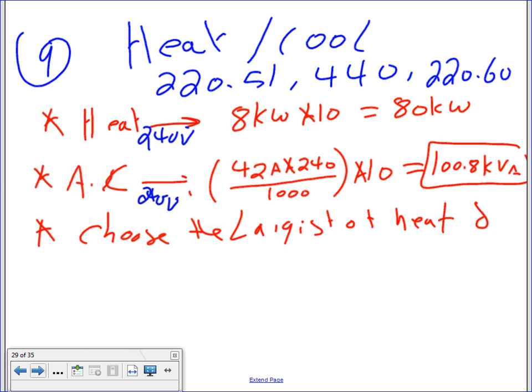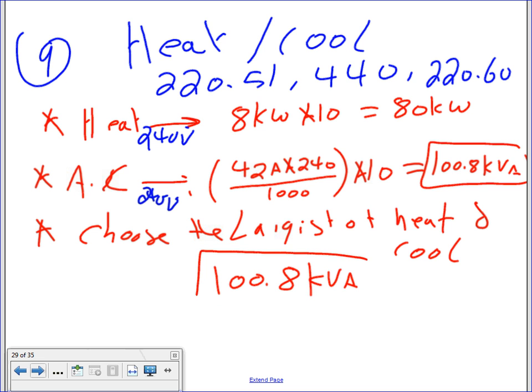Okay, now choose the largest of heat and cool. The largest of the two is this kVA. The cooling is the largest, so that's the one you're going to carry for this step, because it's highly unlikely that you will be heating and cooling the building at the same time. Would you? You must have lost it if you're going to do both.